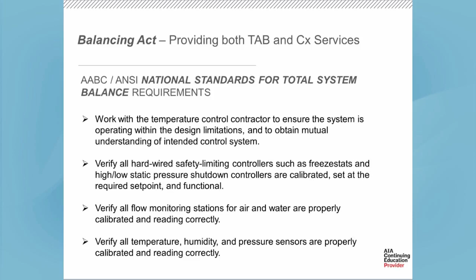Verify all flow monitoring stations for air and water are properly calibrated and reading correctly. There is no one else typically on the project that's more qualified to measure flows than the test and balance firm. So we argue that regardless, that is their function, to check that. And then verify all temperature, humidity, and pressure sensors are properly calibrated and reading correctly. Again, who has the instruments already on site that should be of appropriate calibration and should have the experienced personnel on site to measure these things? That's the test and balance firm.